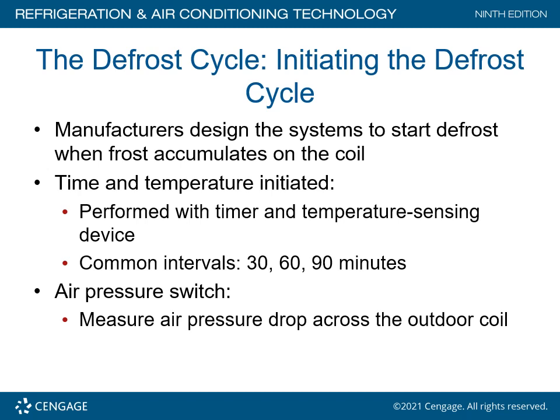Performed with a timer. Today it's all done electronically, not with a mechanical timer anymore. And a temperature sensing device such as a PTC or a sensor. Common intervals are 30, 60, 90 minutes. An air pressure switch measures the air pressure drop across the outdoor coil. In some heat pumps, you'll have an air pressure switch and it will actually sense when the coil is plugged with frost.